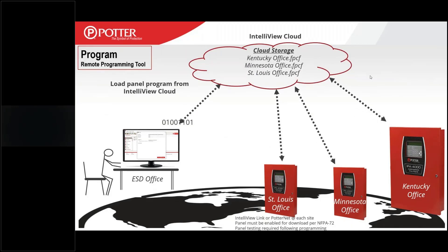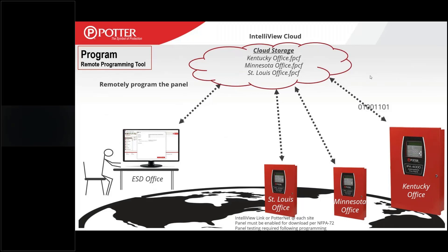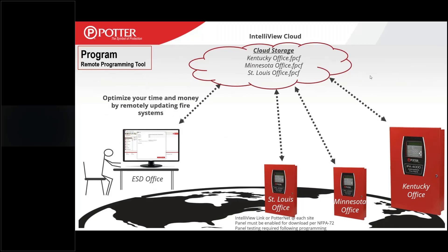Through our Potter programming tool, you can access any one of those panel databases and know exactly how that panel is programmed. Particularly if a panel goes down and you can't find the backup file, and the panel's down so you can't get it from the panel — we have it stored in the cloud under your account. You can get a new panel in there and reprogram. Once it's backed up, you can use our Potter programming tool to grab those files from the cloud, make changes, and send those programs back to the panel no matter where you're located.